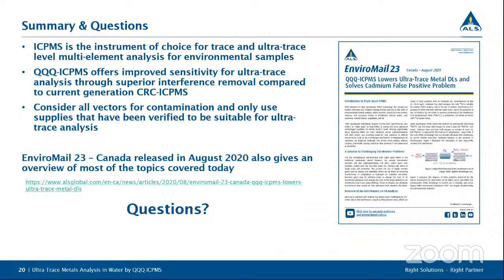She also asks, do you do it in 1 day or in 10 days? We'll typically run the blanks all on 1 day, but then we'll also repeat it on other days so we have them over different calibrations. So we'll try and get more than one calibration, but initially we'll just run 10 on 1 day, we might run 10 another day, and then another 10, so overall you'll have a bigger data set.